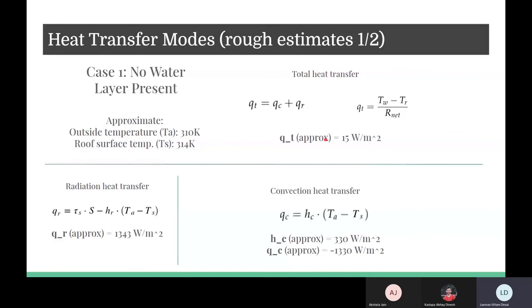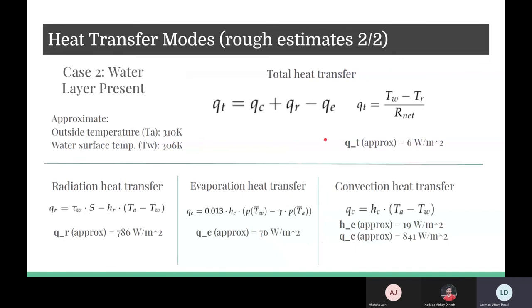Now let us look at the case with a water layer present. The only major difference is the appearance of an evaporative heat transfer term, which depends on the convective heat transfer coefficient and some experimental constant. Taking the same outside temperature of 310 K, solving all equations gives a water surface temperature of 306 K, which is much lower than the 314 K obtained for the bare roof surface. The important result is that the net heat transfer is 6 W/m², which has decreased from 15 W/m² — almost half.